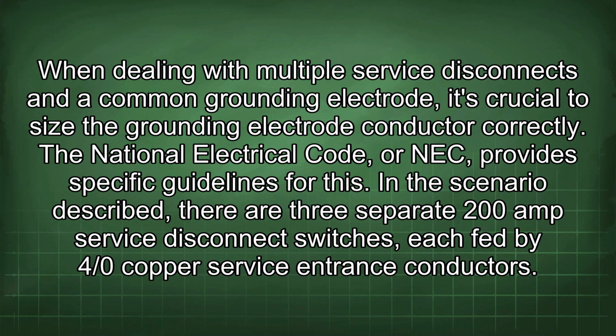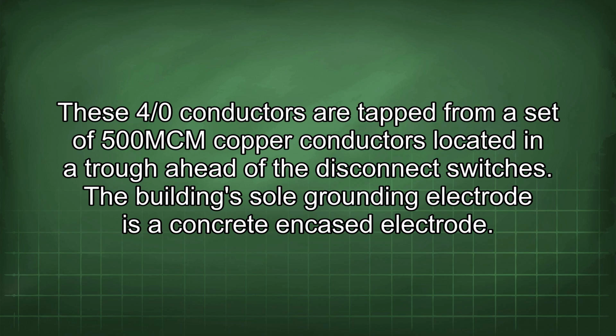When dealing with multiple service disconnects and a common grounding electrode, it's crucial to size the grounding electrode conductor correctly. The National Electrical Code, or NEC, provides specific guidelines for this. In the scenario described, there are 3 separate 200 amp service disconnect switches, each fed by 4/0 copper service entrance conductors. These 4/0 conductors are tapped from a set of 500MCM copper conductors located in a trough ahead of the disconnect switches. The building's sole grounding electrode is a concrete encased electrode.